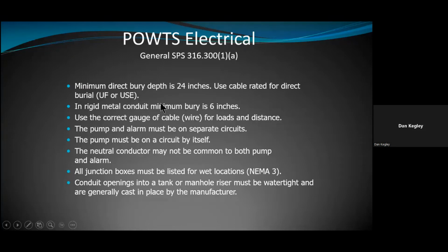Obviously, SPS 316 is the state electrical code, volume 2. I don't know if everybody knew this, but there's two electrical volumes. Volume 1 is Public Service Commission 114, PSC 114, which primarily deals with utility interconnections and transmission lines. And SPS 316 covers all of the premise wiring. So PSC 114 covers all the wiring up to the service meter socket, and everything after the meter socket on the premise is considered premise wiring under SPS 316. DSPS is the one that inspects everything under SPS 316.